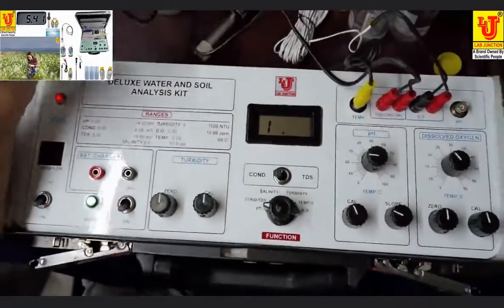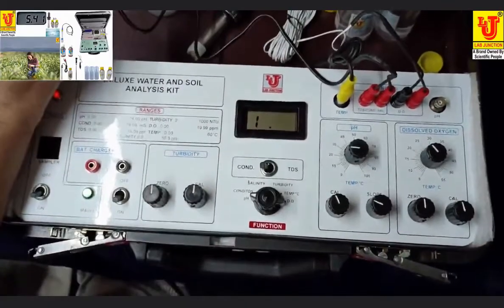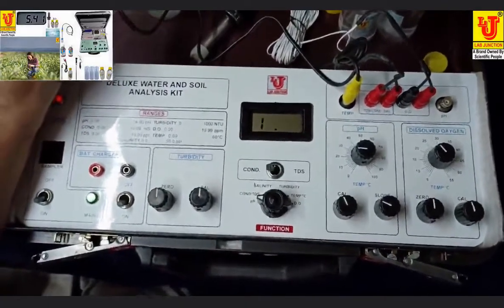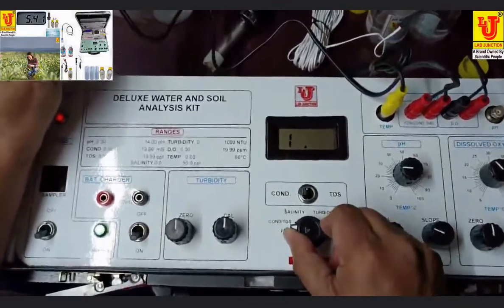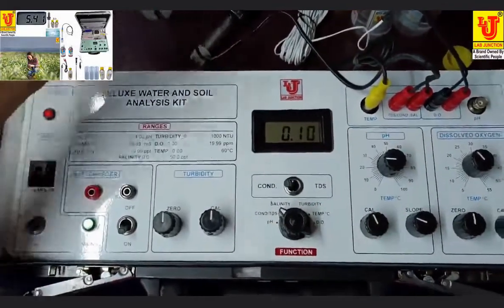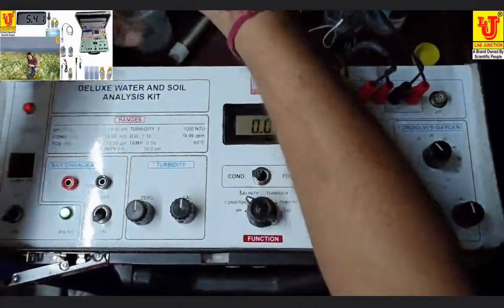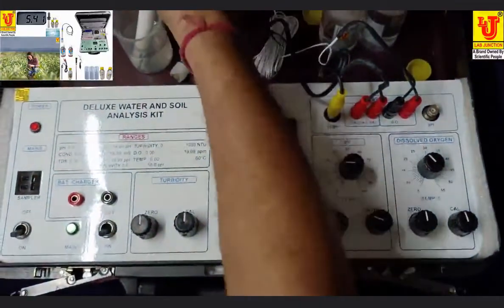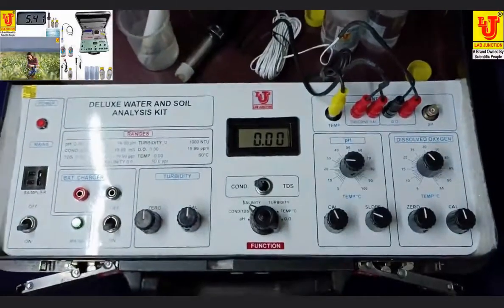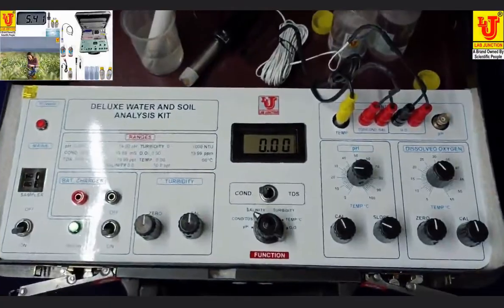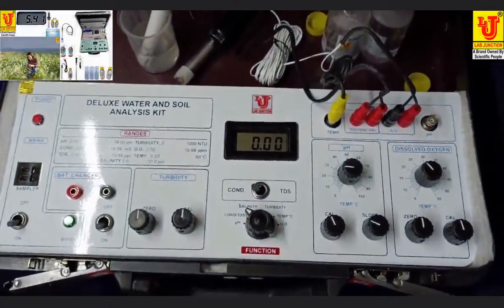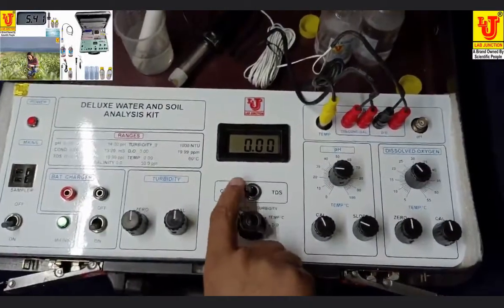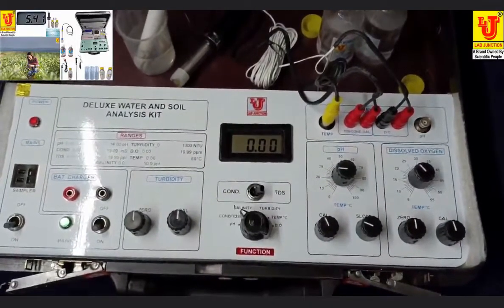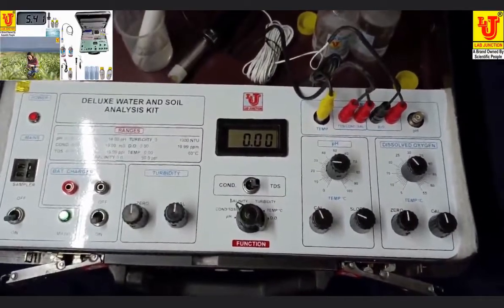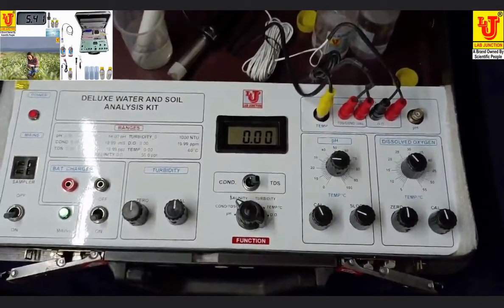Now I am going to conductivity, TDS, salinity. For conductivity, TDS, salinity, I am changing the function control to conductivity, TDS and dipping in the sample. This is distilled water. Distilled water has zero conductivity. If the conductivity value of distilled water is 0, then TDS is also 0.